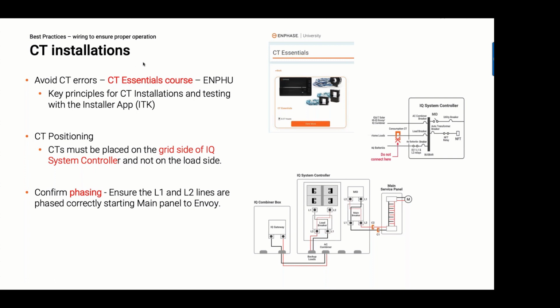The metering system in Enphase's backup systems like energy storage or IQ8 PV is a critical piece of this because the metering system informs the system of when to charge batteries, when to discharge batteries, and programs the inverters to behave. So if the CT installations aren't installed correctly, it's likely that your system is going to behave in a different way than you think it's going to behave. Now, there is a significant amount of CT installation errors, up to 50% occurring in the field at times. So I want to cover some best practices for your attention to help you avoid CT installation errors.